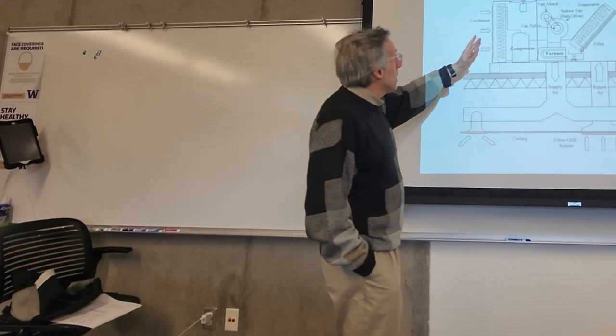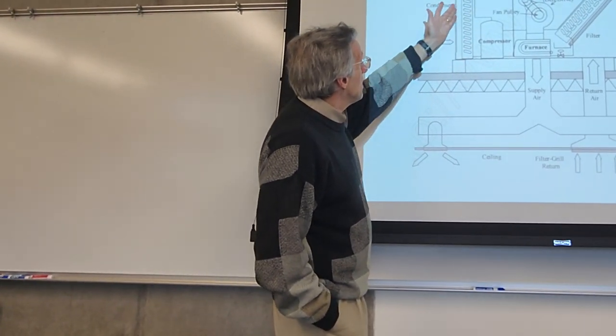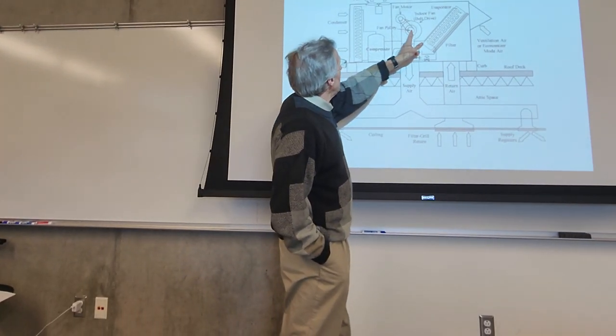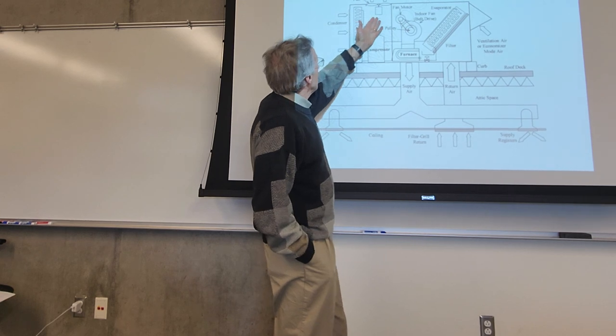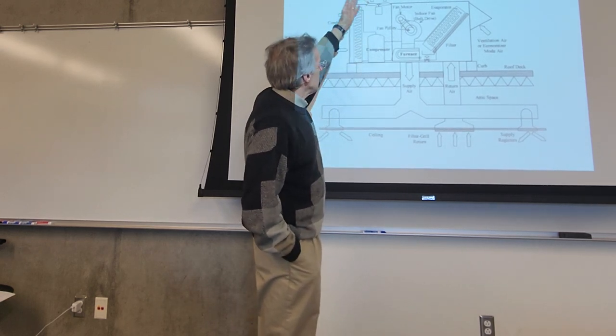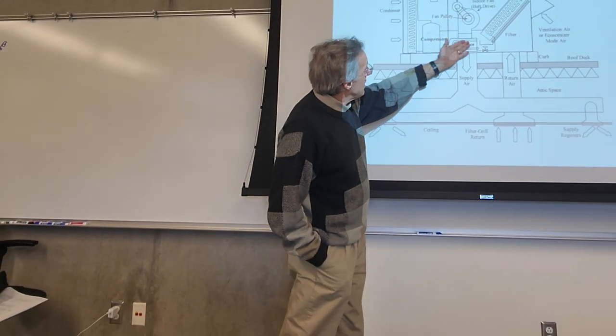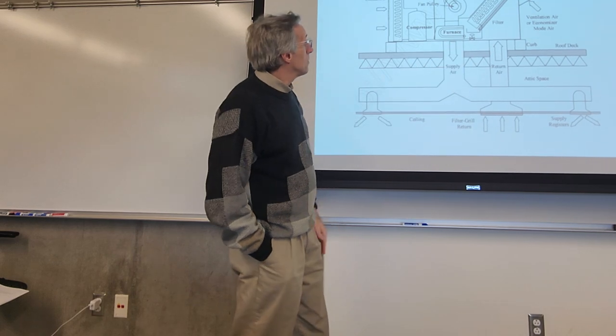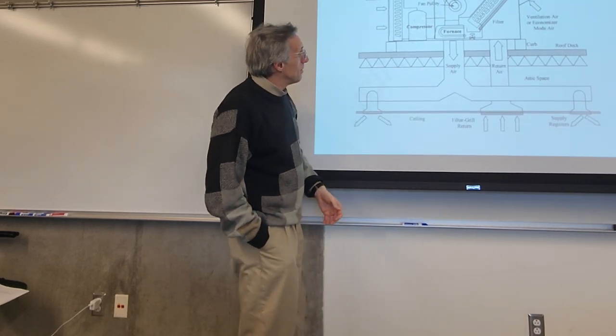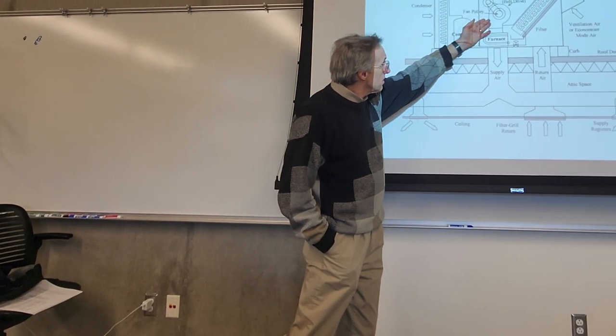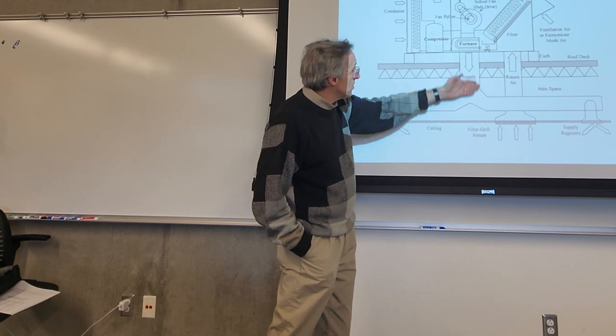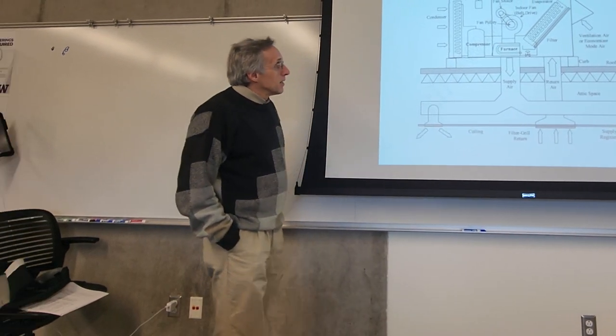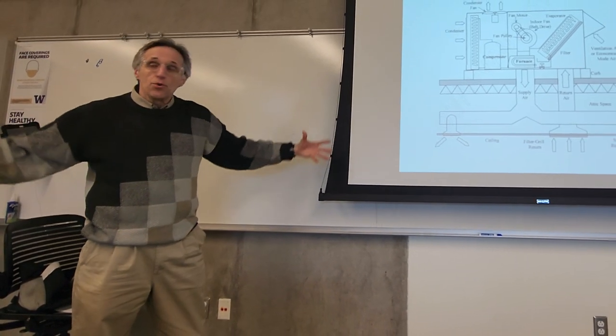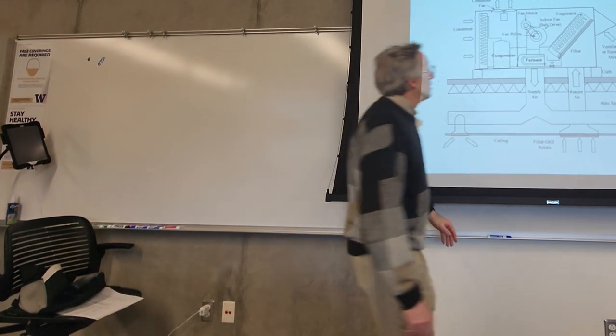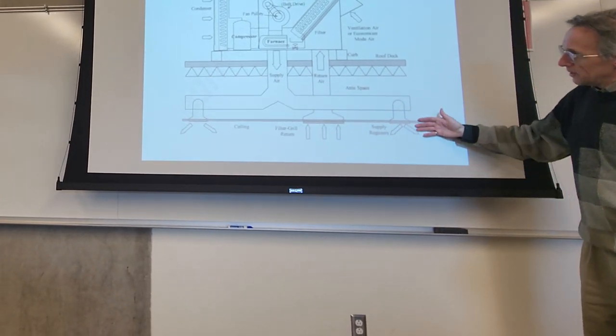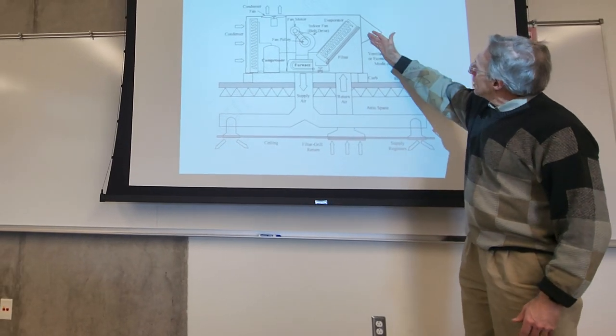And again, all in one, but things are a little more spread out here. You see the condenser coil, the evaporator coil, the fan, the compressor, and the condenser fan, which is rejecting the heat, the ultimate heat rejection, to the environment. And there's a furnace built in as well, maybe a gas or oil furnace, so we can have heating in the winter using the same air handling system. This is a very simple one, not really much ductwork here. Often they sit over the space that they're directly conditioning, usually for single zones, so you might zone off part of the building and it would be conditioned by this system here. Then return air comes in, and the outside air comes in to mix.